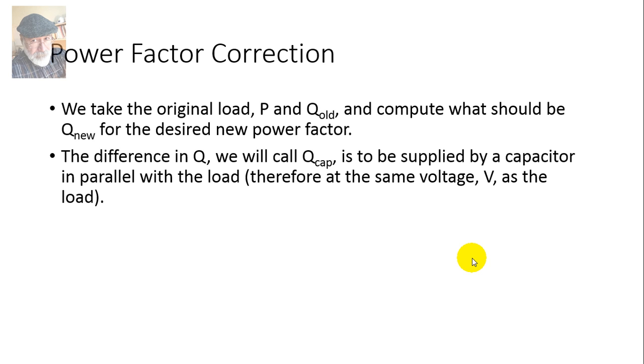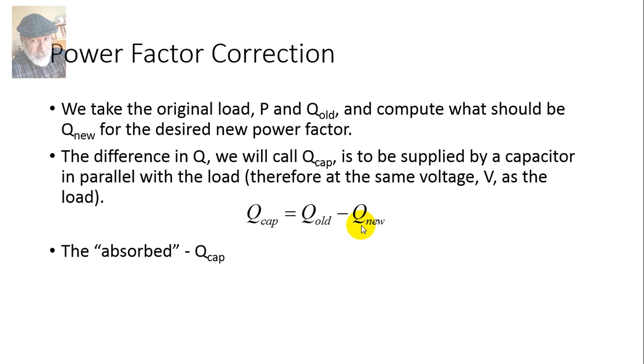The difference between the original Q and the new Q we call the capacitive Q. That is the Q supplied by a capacitor in parallel with the load, at the same voltage as the load. The Q supplied by the capacitor is Q old minus Q new, the final reactive power we want supplied by the utility. But we know that the absorbed Q in the capacitor is the negative of that, because it's absorbed.